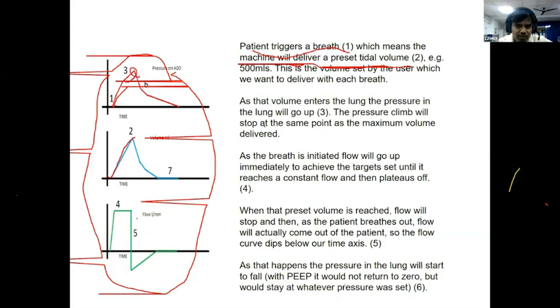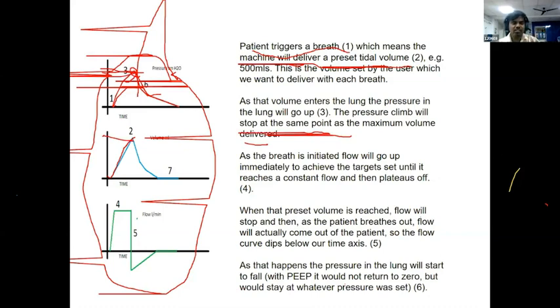And the pressure climb will stop at one point because we fix the pressure up to 40, maximum 35 to 40 centimeter of water. It will not go beyond that. So it will go up to 40, and once again it comes down. You can see here the pressure climb will stop at the same point as the maximum volume delivered. Volume is delivered maximum, pressure also maximum, which we set from outside.